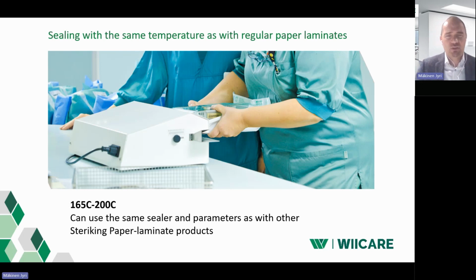The most typical sealing temperatures are around 175 to 185, based on what we know from hospitals, but the range is very wide. We have a special sealing layer in our film which allows a very wide sealing window, meaning you can get a good tight seal across a lot of different temperatures. That's good news for hospitals, since they sometimes can't keep the sealer temperature very stable — this helps them always get good seals.